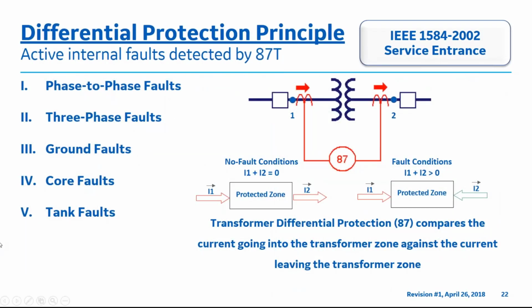Next is the differential protection principle, which is accomplished by a sophisticated 87T transformer protection relay available from several manufacturers. The details of high and low impedance bus differential will not be discussed, but it is the intention of this presentation to briefly discuss an application example per 240.67 code and of an 87T protective relay to help prevent the following fault types: phase-to-phase faults, three-phase faults, ground faults. Item number 4 would be core faults, which refer to the winding insulation of the transformer core. And finally, tank faults, which refers to the clearing of internal faults that would break an oil-filled tank, leading to a large fire.